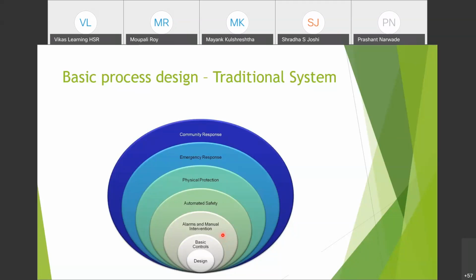In case the system is still going out of control and it's becoming difficult or not possible for a human being to control the system at this point in time, we go into automated safety. This is called level 3 of safety, where the first level is basically alarms and manual intervention, and the second level is automated safety, where it does an override of the system. The final level is when we do an override and are able to bring the plant back into control.